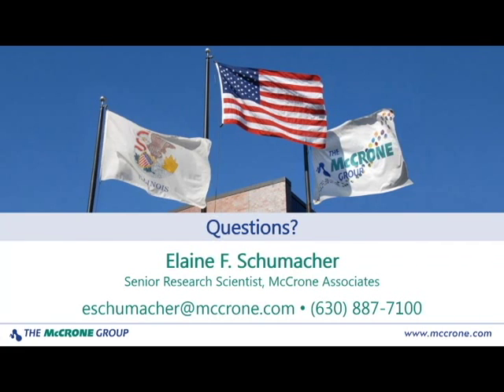But by and large, these are large instruments with a console and a tall column and several computers associated with them. They're typically operated in a room that's kept darkened while you're operating, and you do want carefully controlled environmental conditions. So they're best in a laboratory by themselves and with limited traffic and closed doors. But there is a benchtop model that exists.